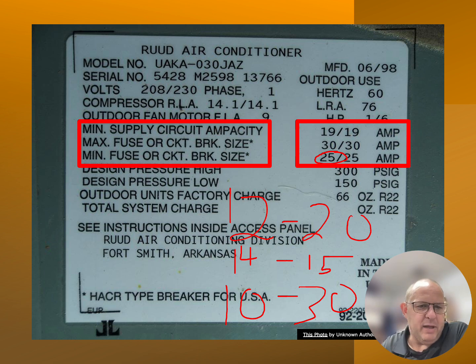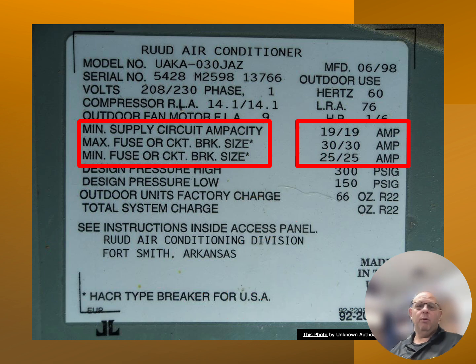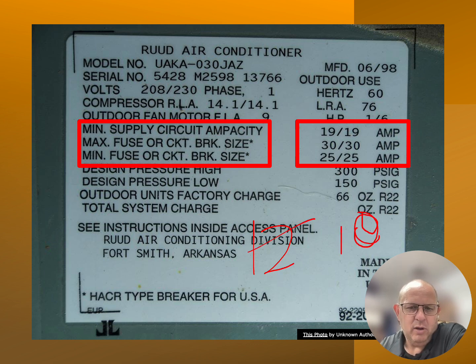So if I was going to use the minimum fuse or the minimum circuit breaker for this unit, I would put it at 25 amps and I would use a 10 gauge wire. Now, what would happen if I decided to put a maximum circuit breaker on this of a 30 amp? That particular unit, 30 amps, could I use a 12 gauge wire? Nope. I would stick with my 10 gauge wire on this unit, and that 10 gauge wire would handle up to 30 amps, and the 30 amp breaker would trip, protecting the wire that's on that particular unit itself.